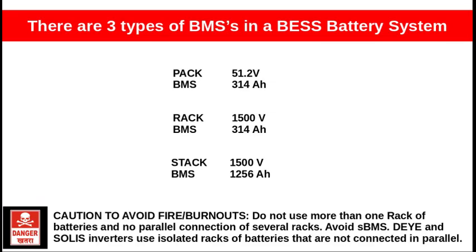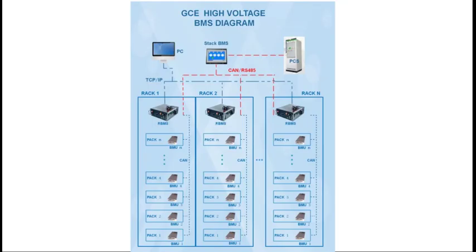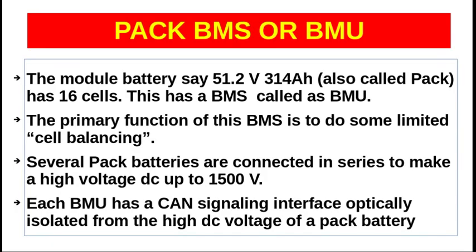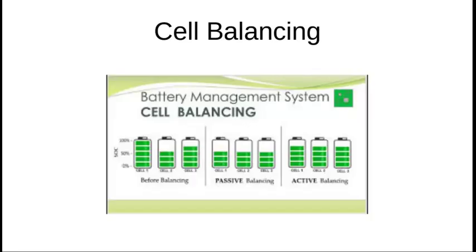Then comes the BMS of the rack. It is also called the high voltage box. The voltage will be high, up to 1500 volts. And the last is stack BMS. It is also called intelligent BMS. It also has the highest voltage and the highest current rating. The pack BMS, also called as BMU, is a slave BMS. The main function of the pack BMS or BMU is to provide a limited amount of cell balancing, and also it has a CAN signaling interface which is optically isolated and connected to the other BMSs.